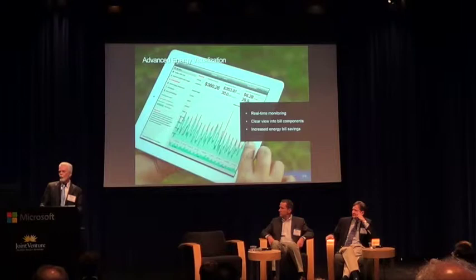We are very active in our partnership with STEM, in that my team uses it as an input, at the moment in manual terms, to our building automation strategies. So in other words, when I'm getting information from them about how expensive the electricity is or where we are on our grid for the day, on our kilowatt consumption for the day, we will trigger load reduction strategies. I have the ability to drop 100 kilowatts of load at any time that I need to, and couple that with a 54 kilowatt system, which STEM is currently deployed on site.